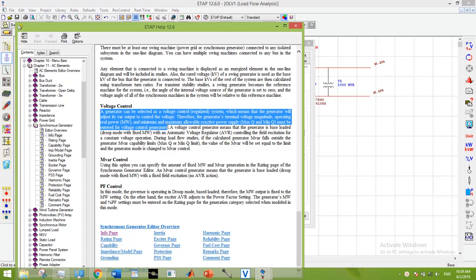So, we face the underexcited and underpowered issue for this voltage control generator because we were actually missing the data which should have been fed before running the load flow. So, it's not too late, let's enter the data now.